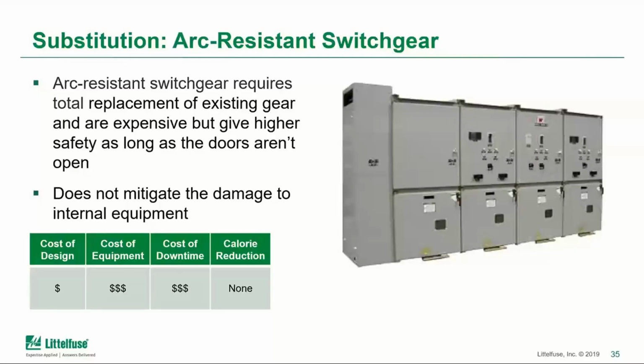Now, one thing to be considered is, if a door is open during maintenance or some other event during an arc flash, then that additional protection is not really going to have an effect. It's going to be neutralized by the door being open. And so here, when we look at our boxes, the cost of design can be relatively low. There are some things to take into consideration, but nothing overly onerous.